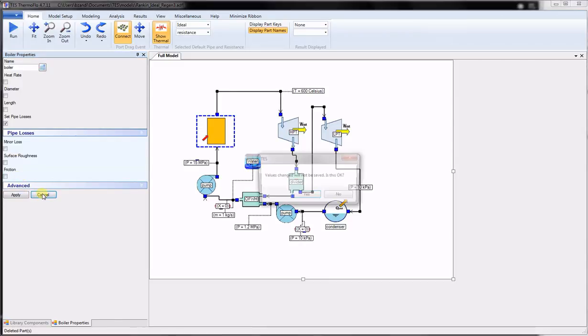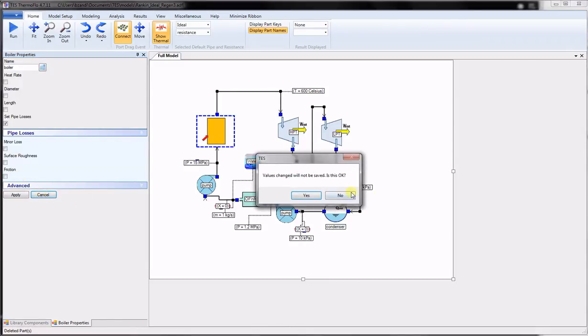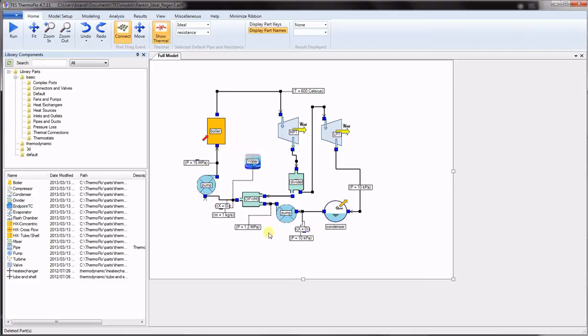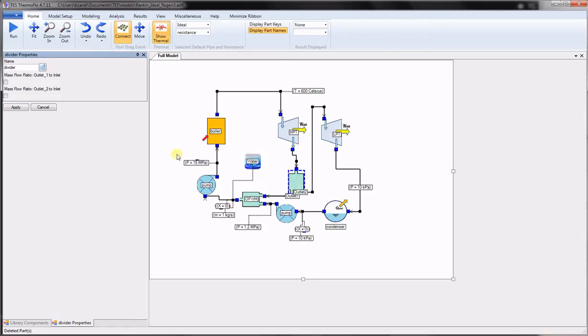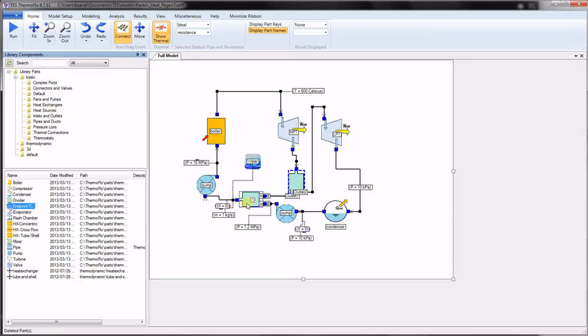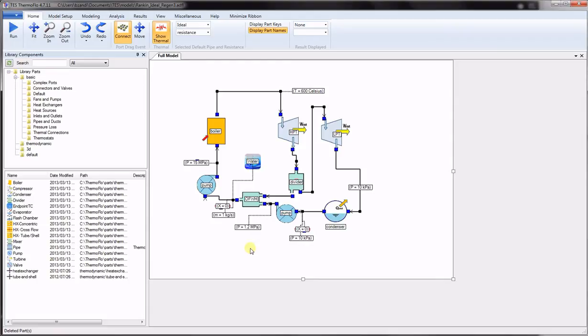Note that the mixing chambers and dividers are used to combine or divide the flow. The mass flow rate for each inlet and outlet may be calculated automatically using the continuity equation if enough information is provided. Otherwise, the user can set them using the component properties form. This represents a significant difference in approach between ThermoFlo standard mode and thermodynamics mode. Recall that in the standard mode, several parts can be connected using a connection point. Whereas in the thermodynamics mode, the user must insert the mixer or divider component for all flow branches.